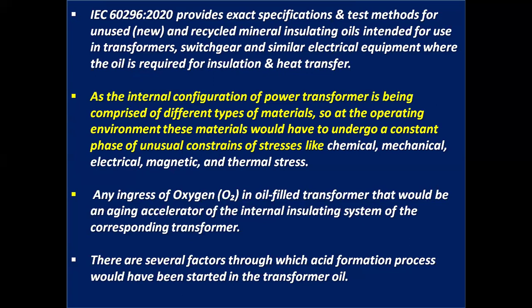at the operating environment, these materials have to undergo a constant phase of unusual stresses like chemical, mechanical, electrical, magnetic, and thermal stress. Any ingress of oxygen in an oil-filled transformer would be an aging accelerator of the internal insulating system of the corresponding transformer.